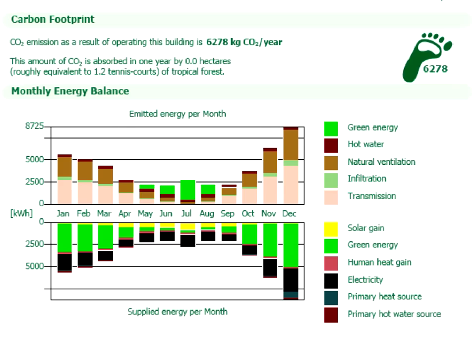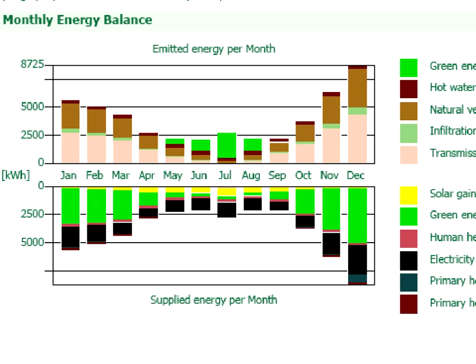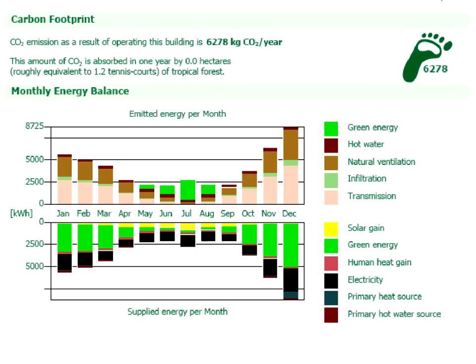Let's have a closer look at the monthly energy balance graphs. Notice that there are hardly any blue areas at the lower part of the graph. This means that there is virtually no need to use any supplied heat source in this building. Heating is provided by the solar collectors and the heat pump, while the collectors also produce the energy needed for hot water generation, and the heat pump is switched to cooling mode during the warm summer months. Both the heat pumps and solar collectors can be used to produce energy for multiple purposes simultaneously.